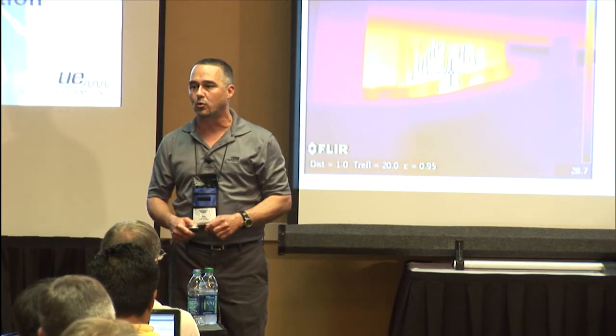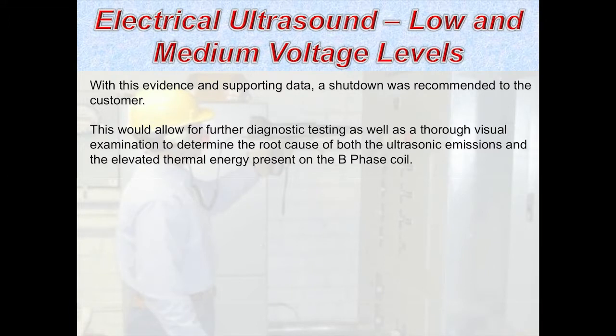In this particular case, it seems as though the origin of that thermal energy is somewhere down inside the core. And that can be problematic because the windings are wrapped around the core. That happens to be the primary side on the inside, and the only thing separating them is that varnish insulation on the windings. So if that starts to deteriorate and degrade, you could have a big problem from an operation standpoint and/or arc flash standpoint. So with this evidence, we convinced the customer, you better take an outage. Due to the redundancies, you're able to shut this down, with a little bit of coordination. It's a nightmare to coordinate things in a hospital or a data center or a lot of places, but it can be done. So we convinced them to shut it down to let us do some other testing on there to find out if this anomaly has caused some type of electrical damage.